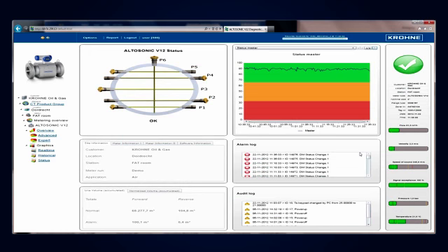We're now under the graphics header and we have here the real-time, historical and status screen. We're in the real-time screen at this moment. And here you can see all the live readings of the meter. You see, for example, in the graph here, the gains per path. You see that a few gains are high. That's paths 3, 5 and 6.